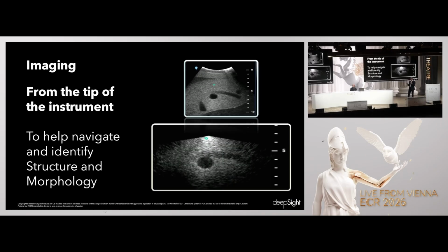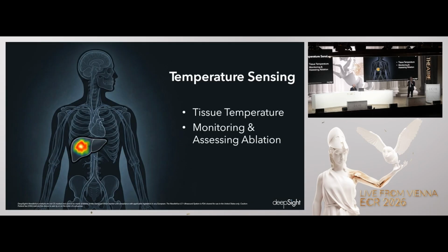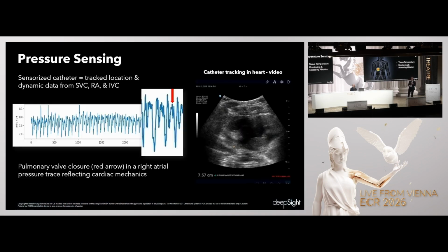The sensor that we've developed is so powerful, it'll pick up the acoustic energy from an ultrasound transducer locally and reconstruct an image from the tip of the instrument. And we've added temperature sensing. We can monitor the temperature to within fractions of a degree. Great for monitoring ablations and assessing the treatment. And we've added pressure sensing.